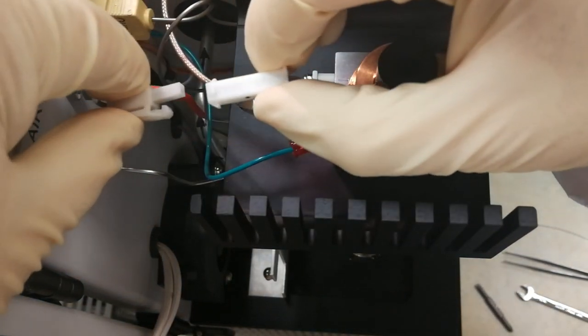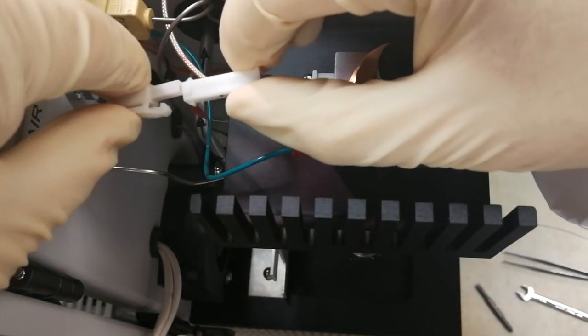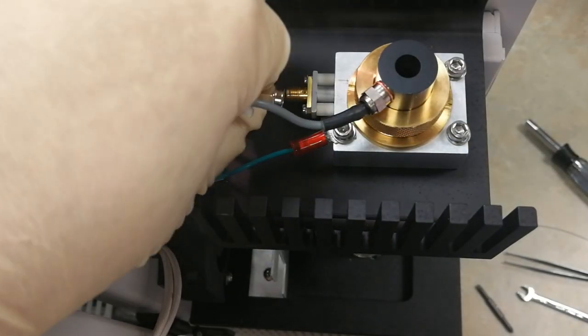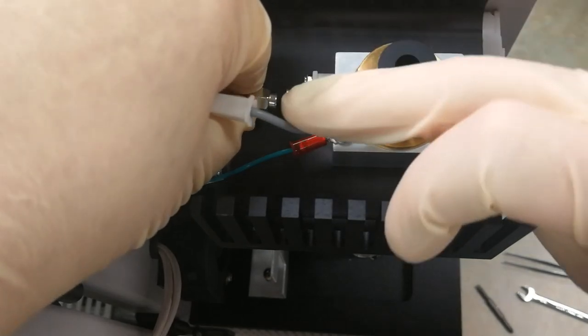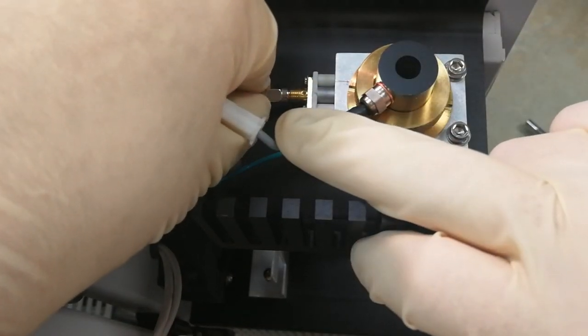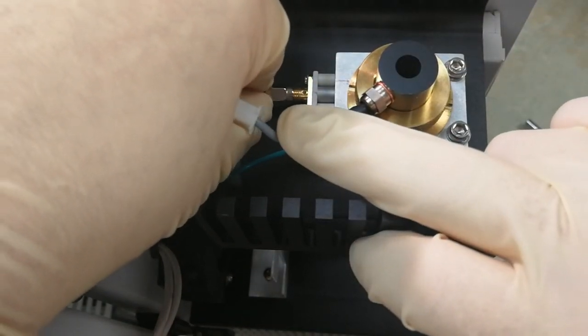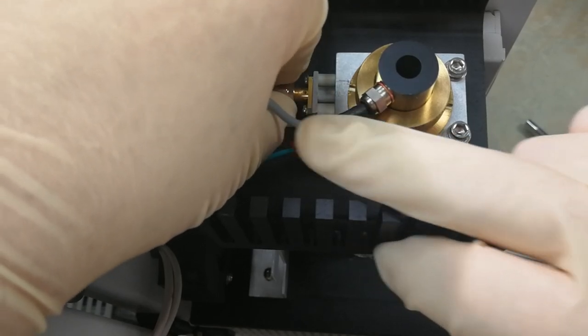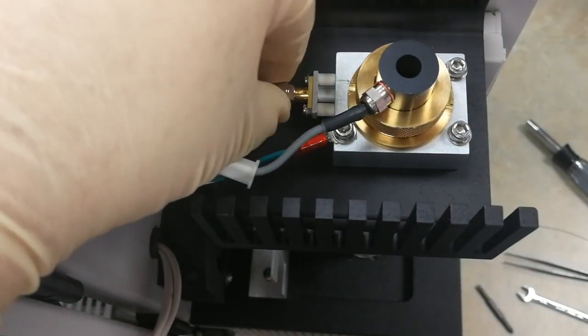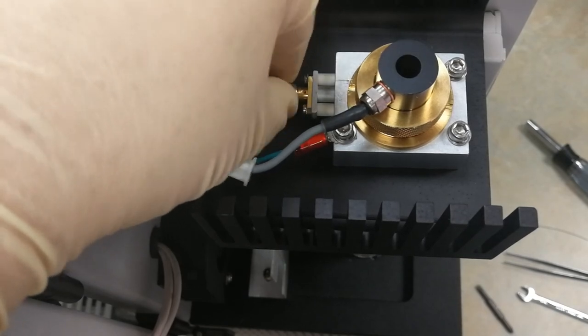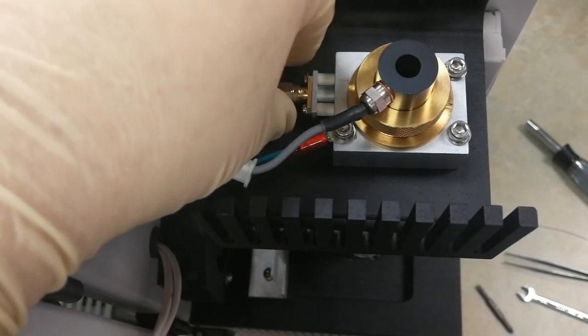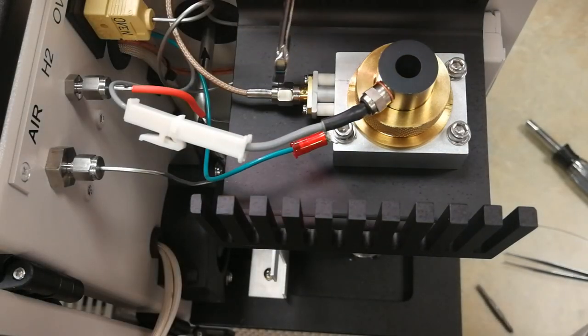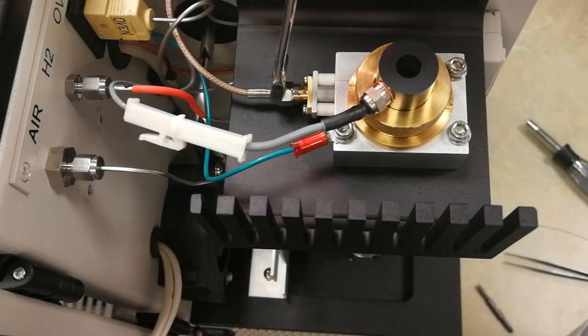Reconnect the igniter wire. Bring the FID signal cable back in. Make sure the little pin doesn't get bent. Reinsert it. Take your 5/16 wrench and just give it a little bit of a tighten. You don't want to crank down on this.